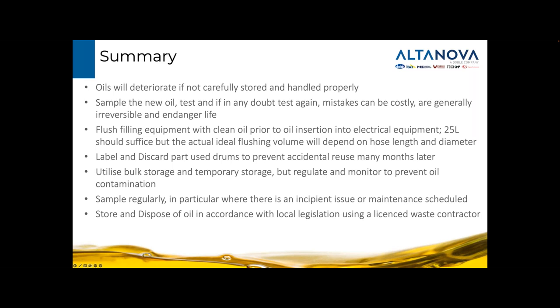Label and discard those part-used drums unless they will be used later for maintenance via mobile processing plant. As soon as you open the drum, you've lost the quality control, so always test the oil before use. Monitor and record your storage activities so that there is a paper trail in the event of an issue to help you find the cause of the issue. Sampling is going to be your best tool to identify incipient issues and get good quality control of the oil. It's a skilled task, so ensure your engineers receive regular training to keep the data representative. Store and dispose of oil in accordance with the local legislation and use a licensed waste contractor to handle your oil and oil contaminated waste materials.